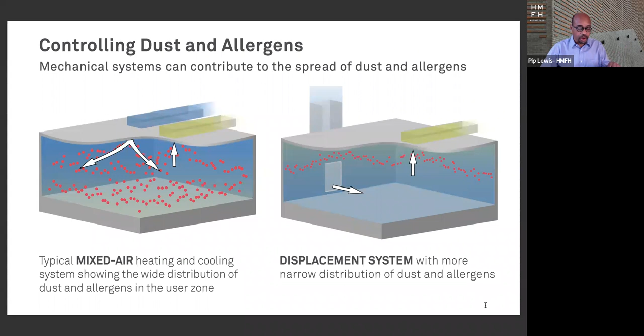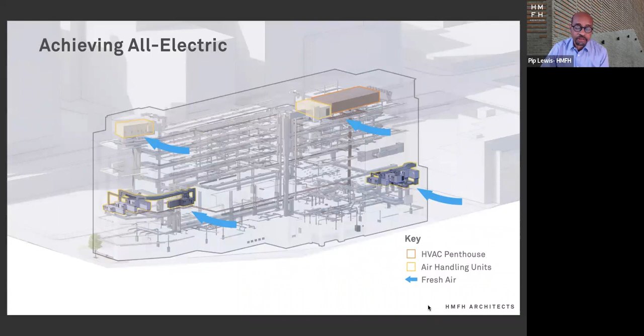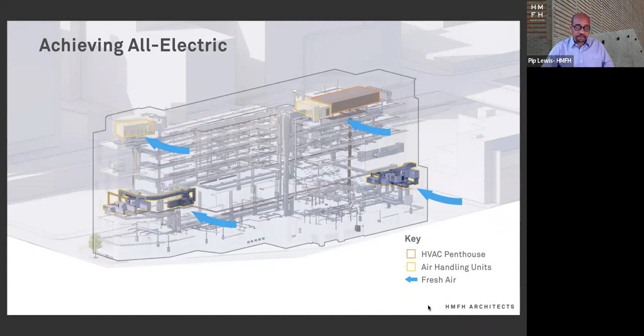But next slide. We did run into a stumbling block. The water source heat pumps that we were trying to use could not extract enough heat on the coldest winter days to sufficiently heat the school. And so we needed to supplement with supplemental boilers, which are located on the top of the building, that long gray box on the right-hand side. And these either needed to be powered by electricity or gas-fired. Next.